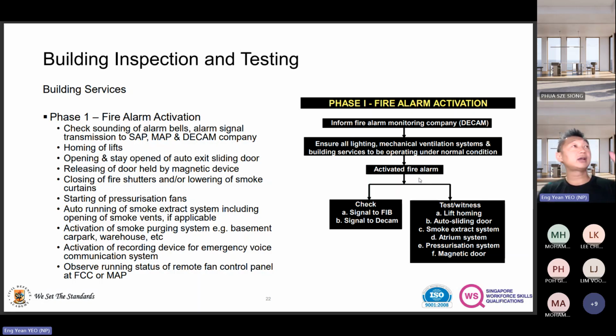So after activating the fire alarm, you definitely check the FIB, the fire indication board - the sub alarm panel, the main alarm panel - is there an indication, and is it correct? This is always done monthly because the fire alarm system needs monthly checks. Then does the signal go to DECAM? From my understanding, the signal goes to DECAM and at the same time to SCDF, the nearest fire station. Why 2 minutes? Because once this is activated, SCDF treats it as an emergency and is on the way. The 2 minutes is to make sure SCDF can confirm it's a false alarm and can U-turn back. But if we reach there and it's a false alarm, then the activation fees will be charged to the respective landlord.